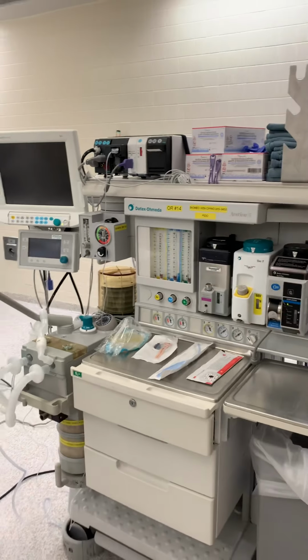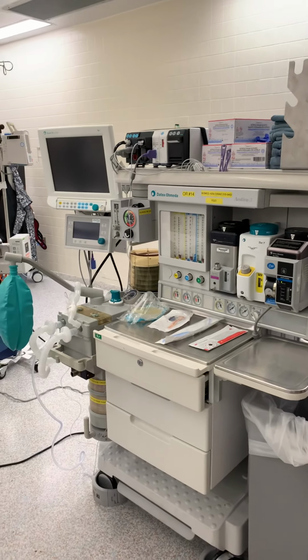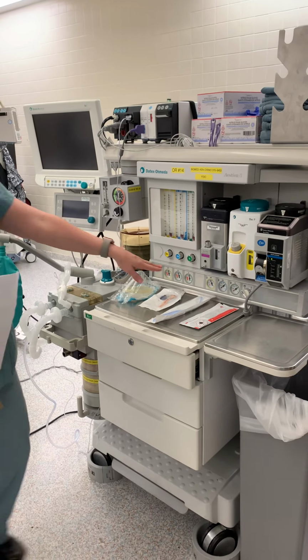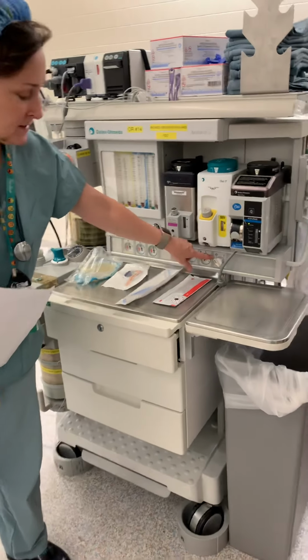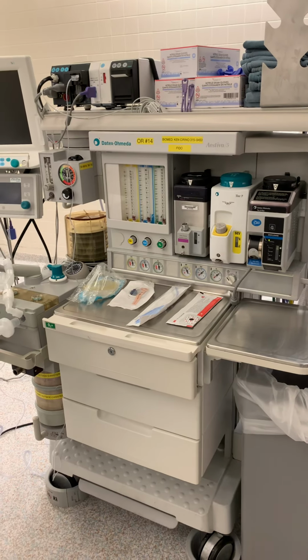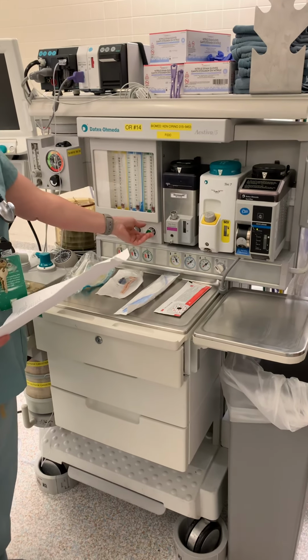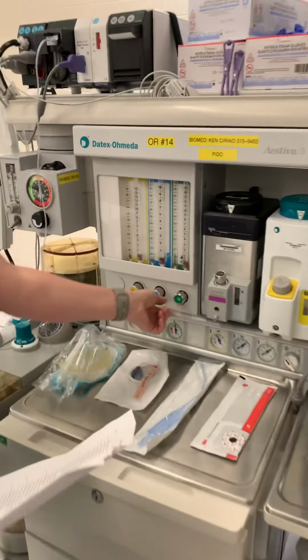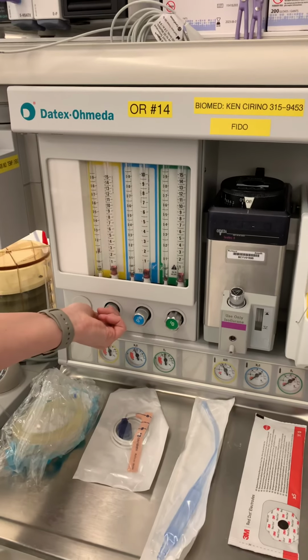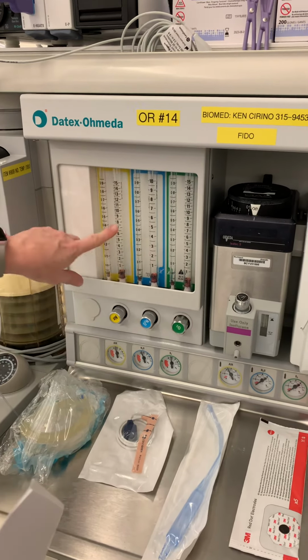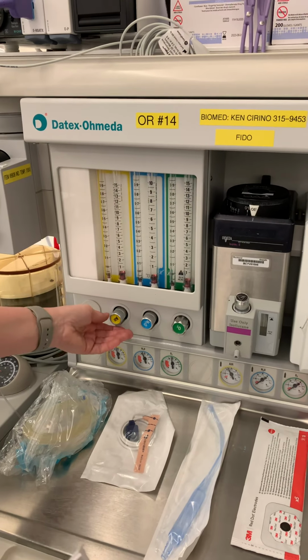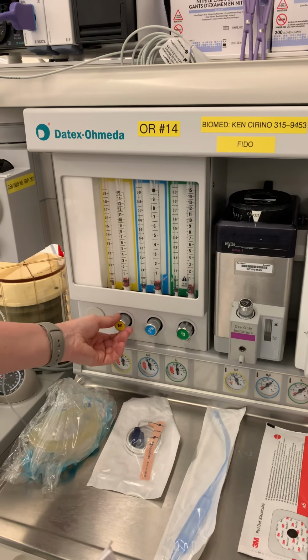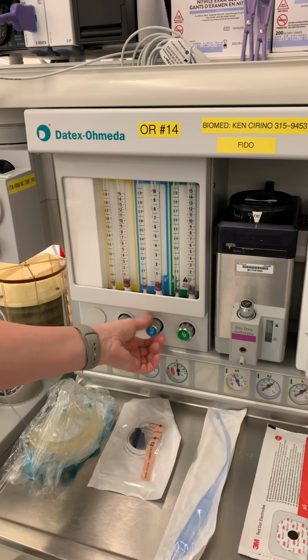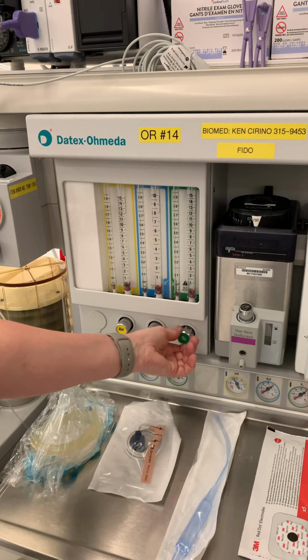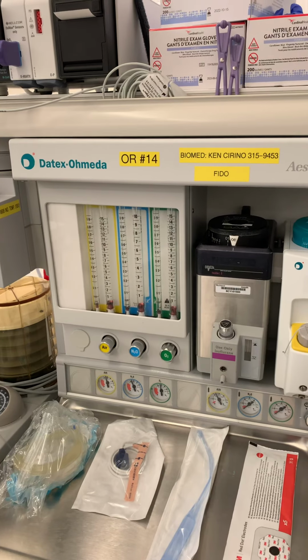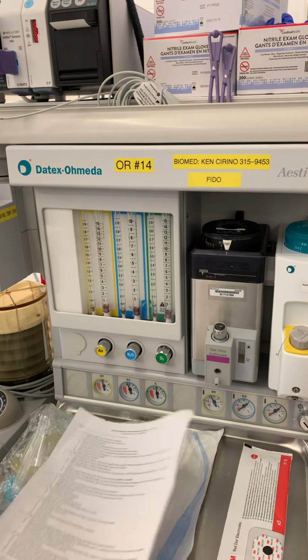Number two is you want to test your low pressure system. While your machine is still off, we're in the off position, you want to bleed out whatever air is in the system. So you want to turn all your flow meters 1.5 turns to the left. And if you noticed just briefly, the flow meter bobbed up and then went back down as all the air left the system. So now you should have no air hopefully left in the system.